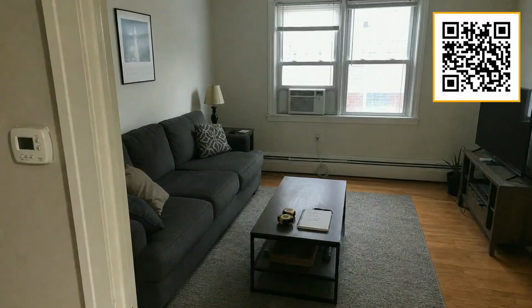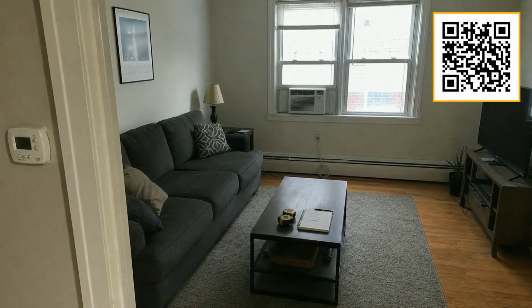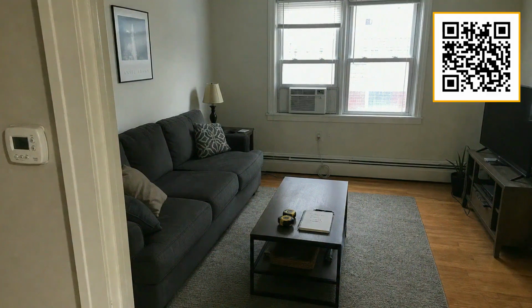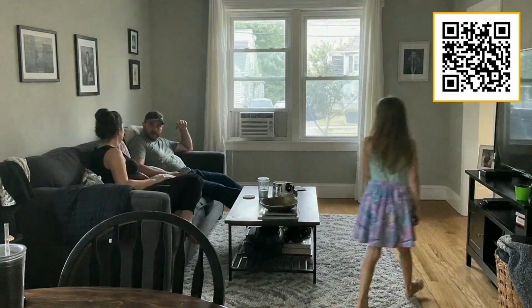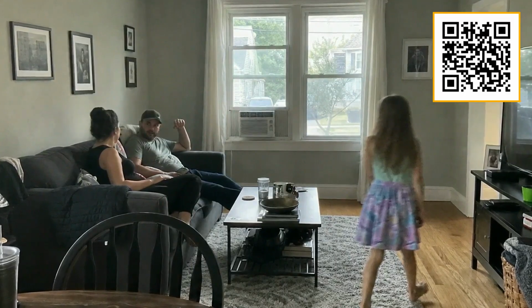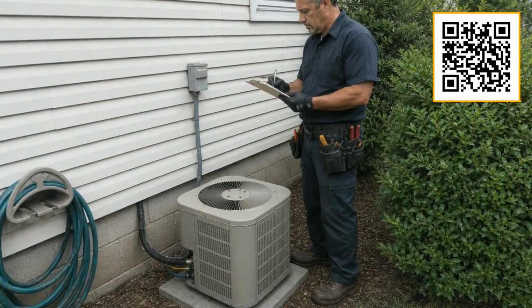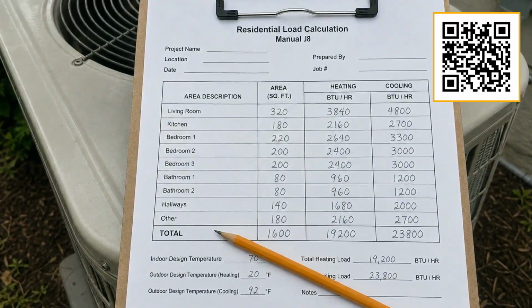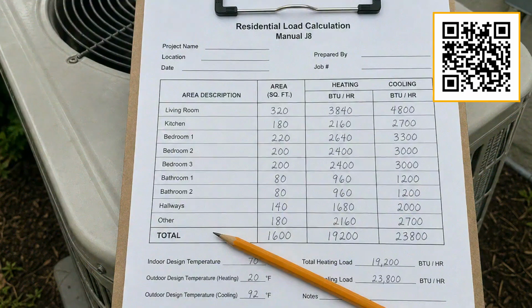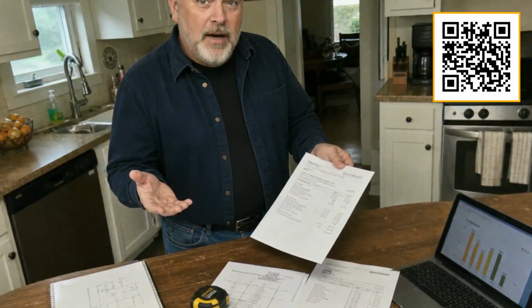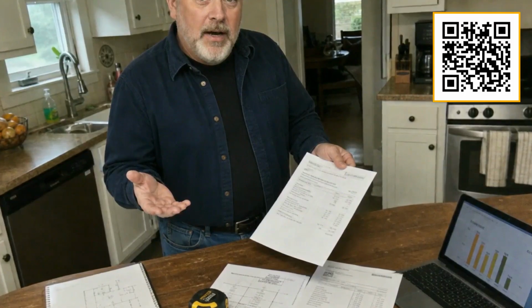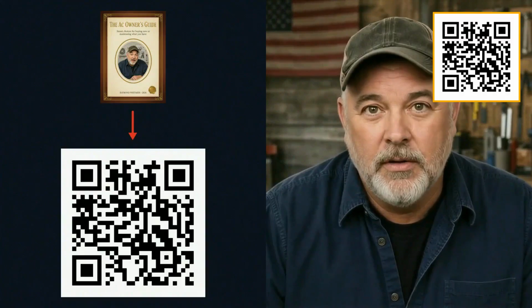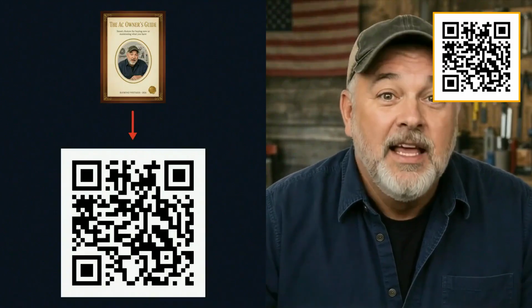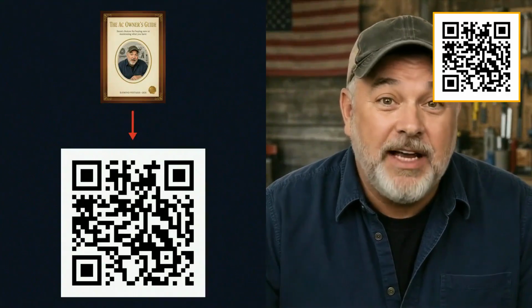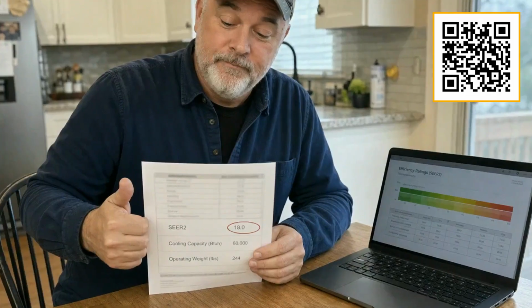The industry uses BTUs, British thermal units, to measure cooling capacity. A rough starting point that holds up reasonably well is around 5,000 to 6,000 BTUs for a small room up to about 250 square feet, scaling up from there. But that number needs to be adjusted for ceiling height, sun exposure, how many people regularly occupy the space, and regional climate. For a whole home central system, a proper Manual J load calculation done by an HVAC professional is the honest standard, not the shortcut of just matching the size of whatever unit came out. If a contractor gives you a quote without doing that assessment, I would be skeptical of their work. The guide linked in the description below covers the sizing math in plain language, so you can go into any contractor conversation with a baseline understanding of what your home actually needs.